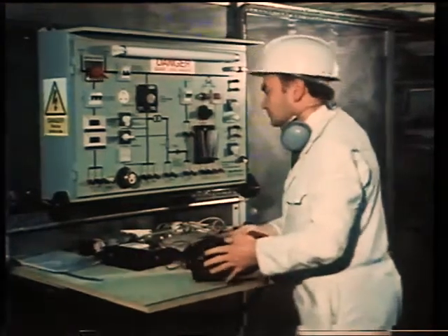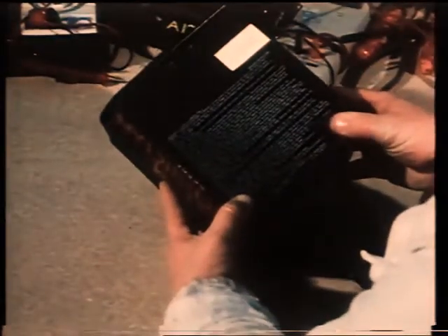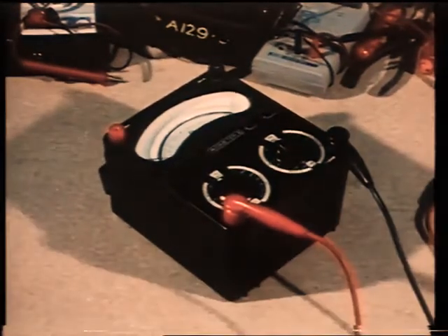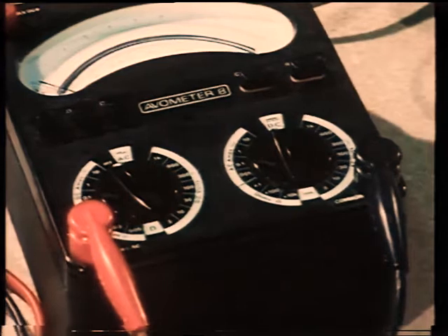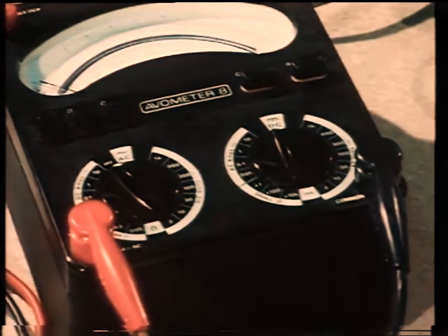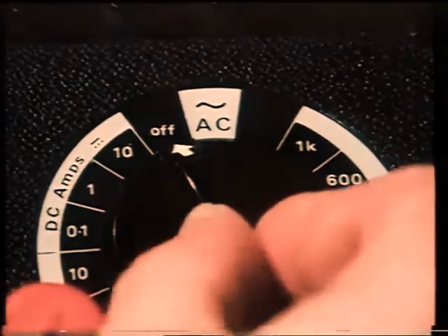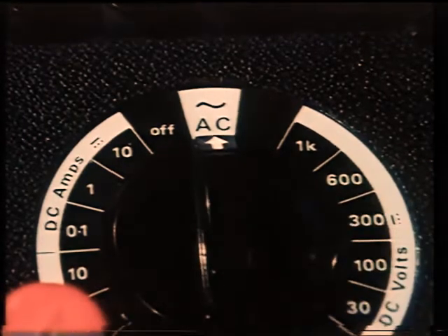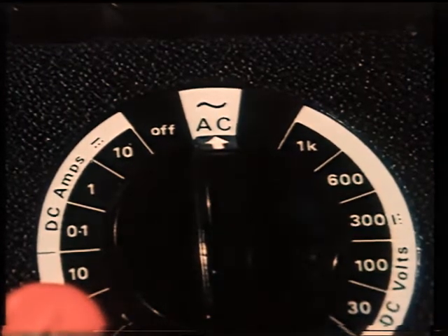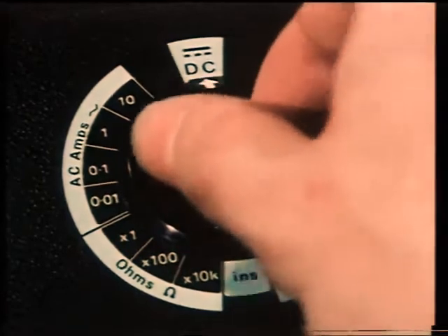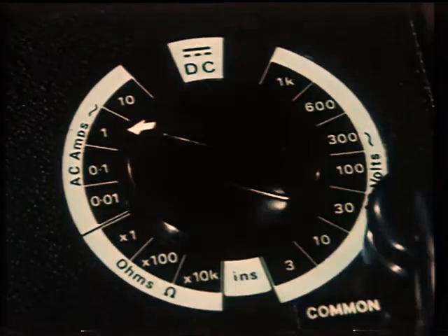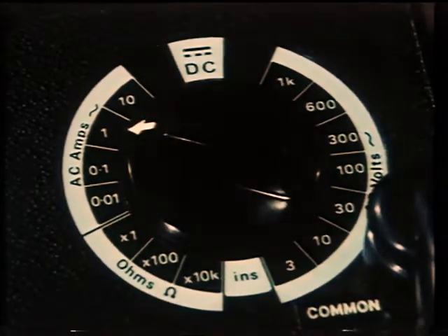First, an analog meter. For easy reference, the setup procedures are listed on the back of the meter or in the user manual provided by the manufacturer. Basically, the two dials work in combination when setting the meter up for any of its functions. Here, the meter is being set to read AC current by pointing one dial to the AC symbol and the other dial to the values range, in this case up to 1 amp.